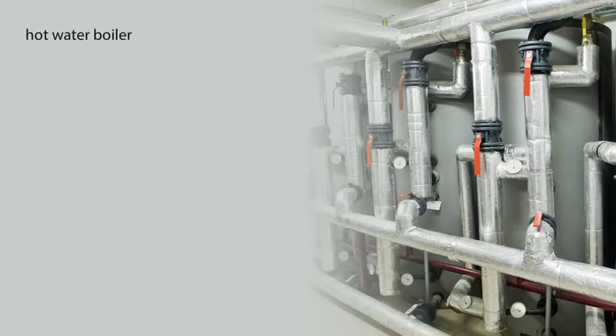Hot water boilers are rated as low or high pressure. Most hot water boiler systems operate at 30 PSIG or less for heating homes and commercial buildings. High pressure, high temperature water systems are used principally in large central plants.